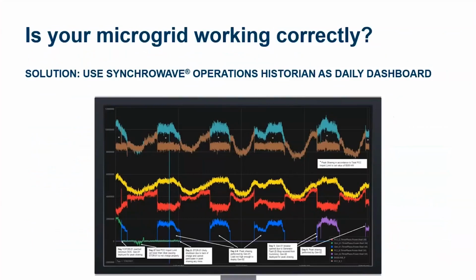One of the biggest questions that any owner of a microgrid needs to answer daily is, is your microgrid working correctly? Is it achieving the objectives I asked of it? Am I achieving my return on investment? At SEL, we use Synchrowave Operations Historian as the daily dashboard to show us and our customers that we are achieving our objectives. Here you can see a plot from a microgrid put into service. The cyan or light blue line on top is the total load. The brown is the amount of load imported from the utility.